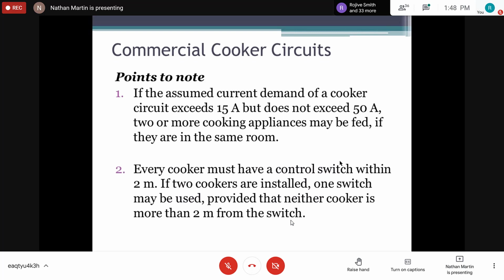Points to note about our commercial cooker. If the assumed current demand of a cooker circuit exceeds 15 amp, but does not exceed 50 amp, 2 or more cooking appliances may be fed if they are in the same room. So it means that if it's not over 50 amp, right, you can feed more than one appliance from that circuit.